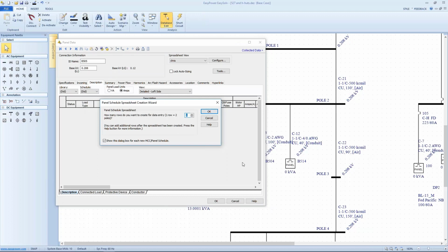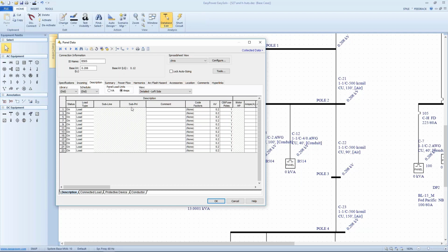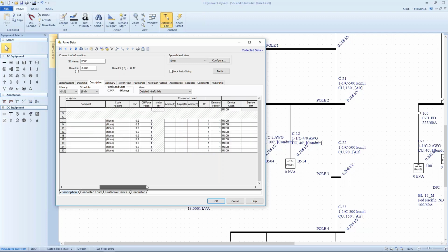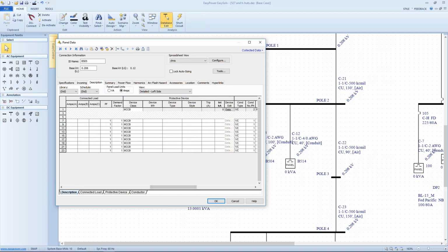In this particular case, we know that the sub panel comes in on the first three circuits, 1, 3, and 5. So let's say this particular panel has 12 rows. We're looking at the left side. Here's circuit 1, and we know, rather than a load or a motor, that this is going to be a sub panel. So as we tab out of here, we tell it which cable leaving this panel we need to connect to, and we know it's A to B. And we also know in this case it's going to be a 3-phase cable. And so by doing this, we've at least let the tool know how the connections to that second downstream panel work. But also by doing this, we've illuminated the data device. So this is the circuit that's going to be feeding that particular panel.